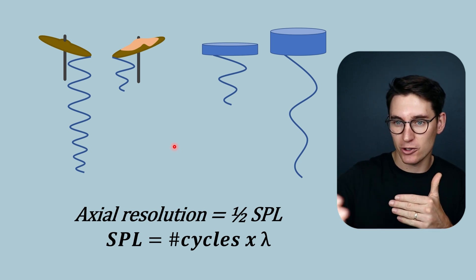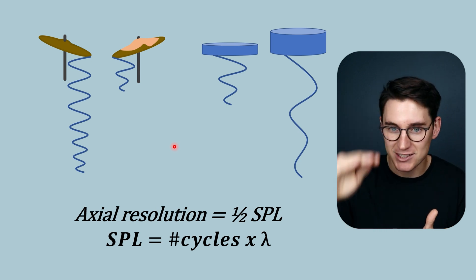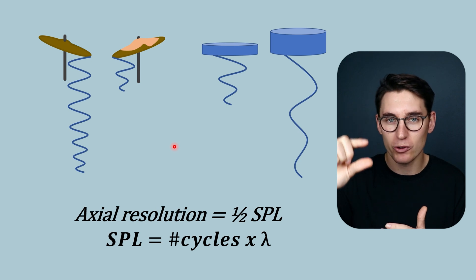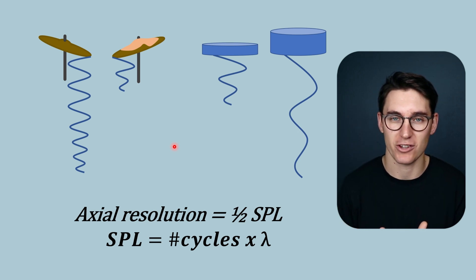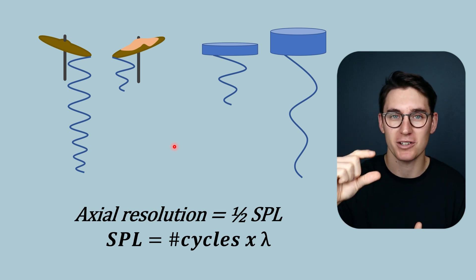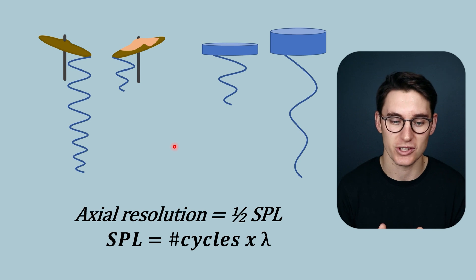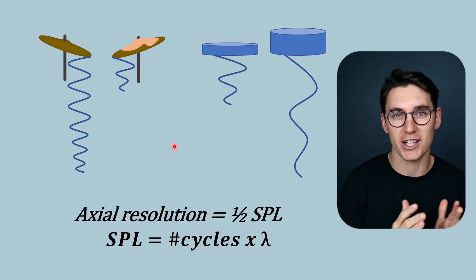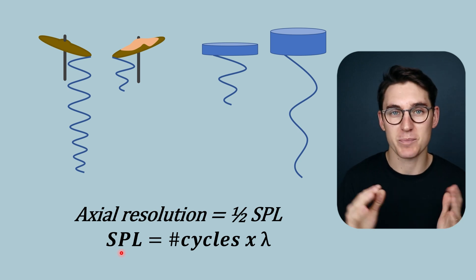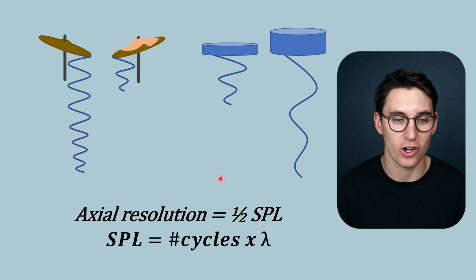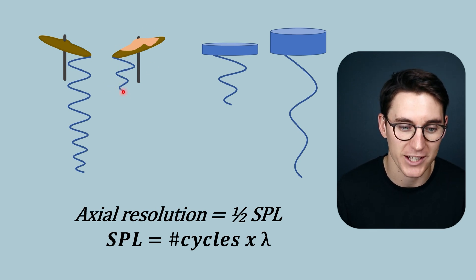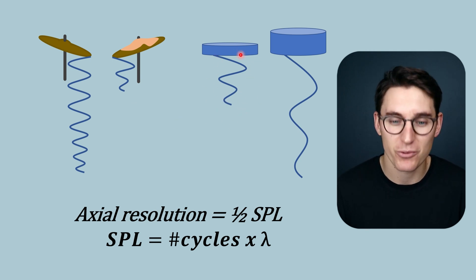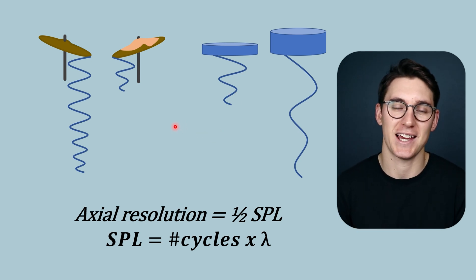Importantly, axial resolution does not change as we go deeper into our ultrasound image — it remains the same regardless of depth. We don't lose frequency as the ultrasound pulse travels through tissues; we lose intensity, but the spatial pulse length doesn't change as it heads into tissue. The only thing that changes our axial resolution is our spatial pulse length, which is related to the quality factor of our beam, the amount of dampening, the number of cycles in the pulse, and the wavelength — or equivalently, the frequency — of our ultrasound beam. Higher frequency means better axial resolution.